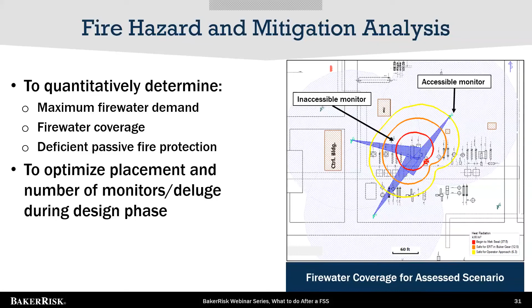Finally, you can also utilize your jet and pool fire thermal radiation predictions for fire hazard and mitigation analysis. You can look at those scenarios and quantitatively determine your maximum fire water demand, your fire water coverage, whether you have deficient passive fire protection, and also optimize placement and number of monitors and deluge systems during the design phase of projects.